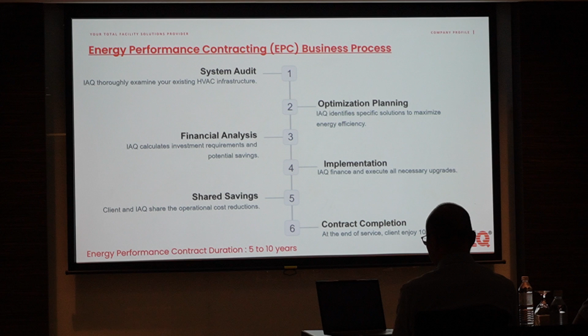So this is our first energy performance contract, for the KLCC district cooling system. There was oversizing of the pumps, so they were operating inefficiently. We invested to optimize the pumps, and each pump's consumption went from 430 kilowatt to just over 380 kilowatt — a 50 kilowatt saving, across around 8 pumps. After that, the plant started operation and we began getting the savings.